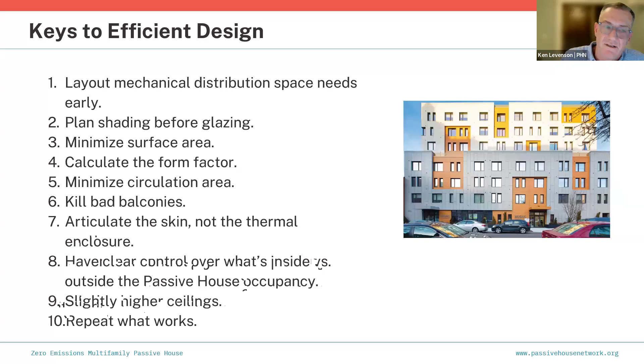Layout mechanical systems needs early—probably all architectural projects should do this when we start out, but too often we've all seen it: you're designing away and nobody's really laid out the mechanical systems, and then they're getting shoehorned in. It's hard enough for typical buildings, but the big issue with passive house buildings is you have a much more extensive and space-needy ventilation system, because the ventilation is a core driver of the ultimate performance and quality of the building.